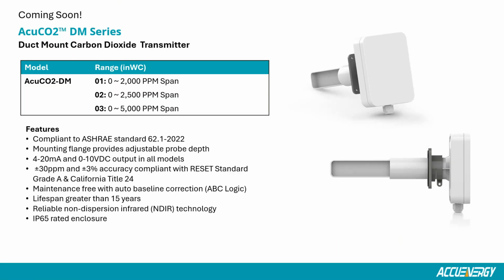We have the gasketed mounting flange to provide the flexibility of adjusting the insertion depth of the probe when you need it. It has both 4 to 20 and 0 to 10 VDC outputs in one model. It has the higher accuracy, plus or minus 30 ppm, and that is compliant with the RESET standard grade A and California Title 24. All of our CO2 sensors utilize non-dispersion infrared technology, the NDIR technology, which has been tried and true for years now.